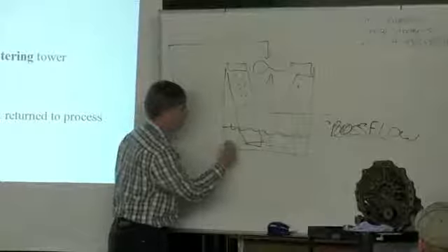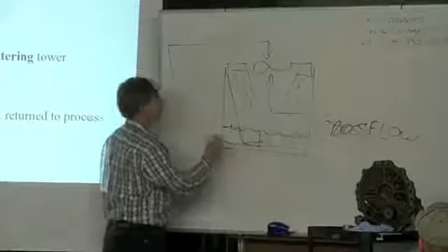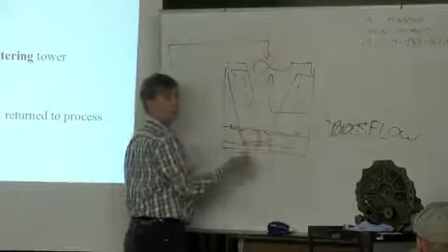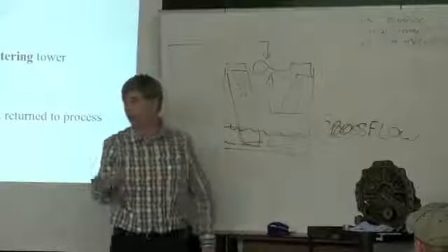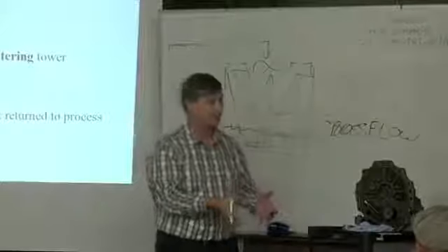If the water level is too low, then all of a sudden, instead of the air being drawn through the fill and out the top with your fan, air is going to take the path of least resistance, right? Unless you get that smart air that knows where to go, and I haven't found that air yet.